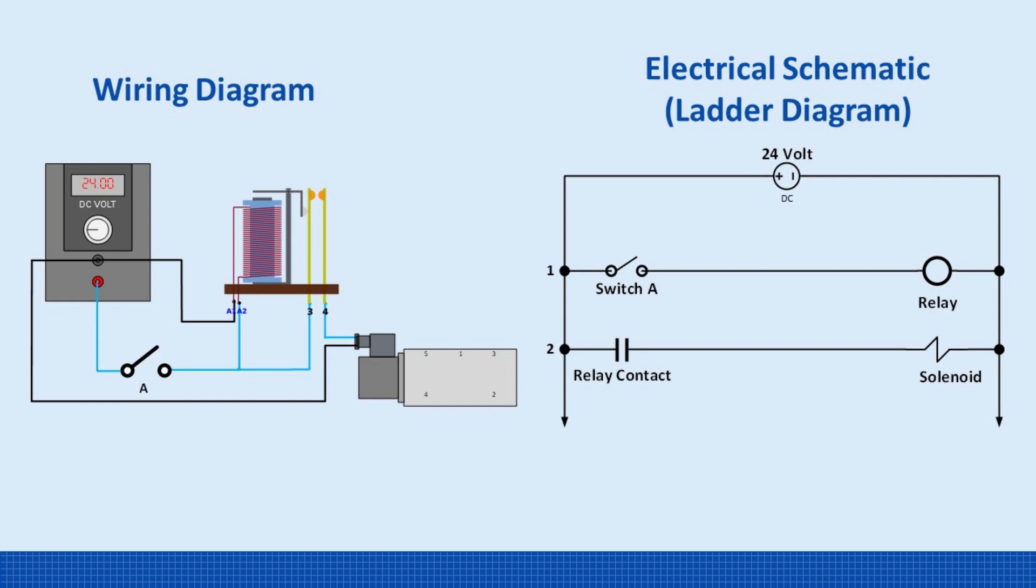On the first rung, when the switch closes, it energizes the relay coil. Then on the second rung, the relay's normally open contact closes, and that powers the solenoid valve. So when the relay is energized, its contacts close, allowing current to flow to the solenoid.